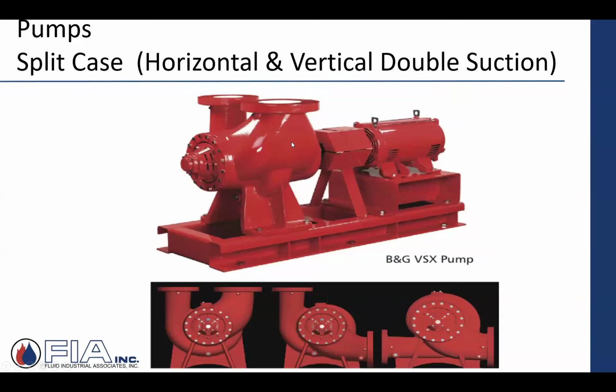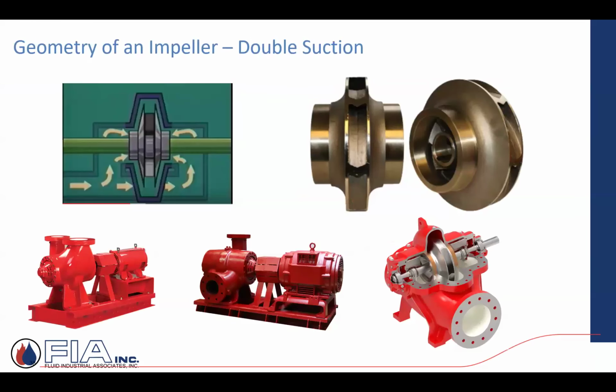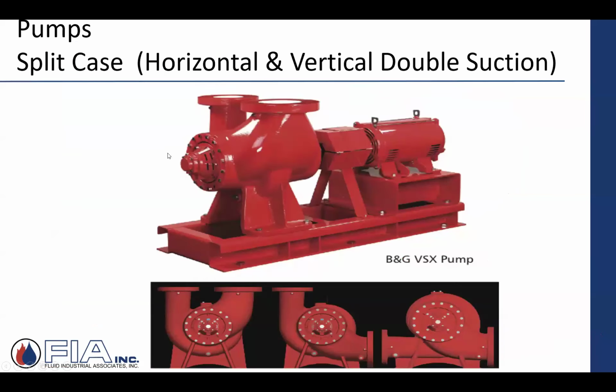And on the inside, there is a splitter. There's actual casting, and it's taking that water and it's forcing it to split and then enter into that impeller on both sides. So this splitter here takes that suction and equally splits that flow in half so that it enters on either side of that impeller. So that's your horizontal or vertical split double suction pump.